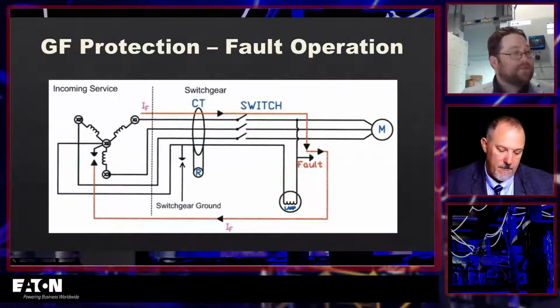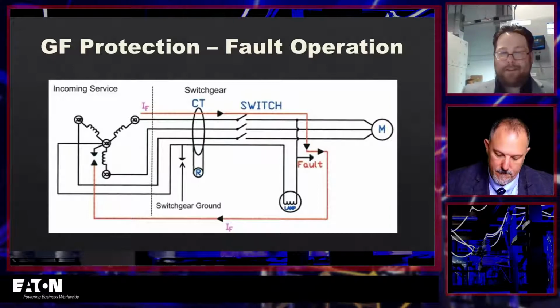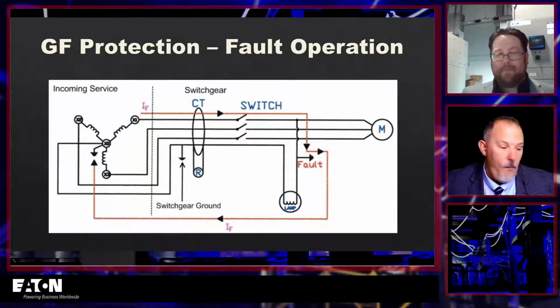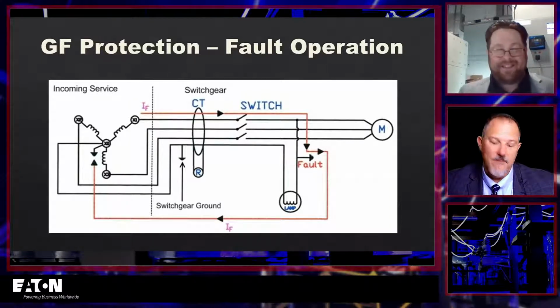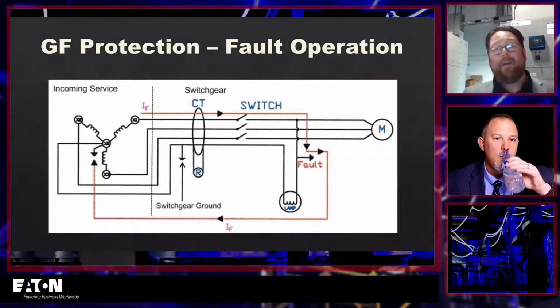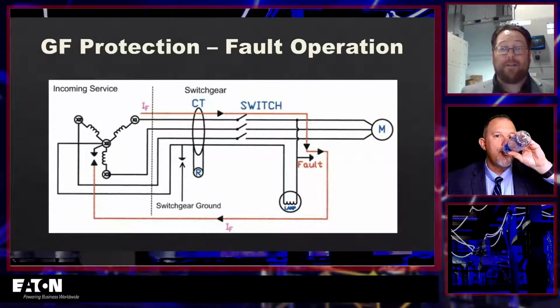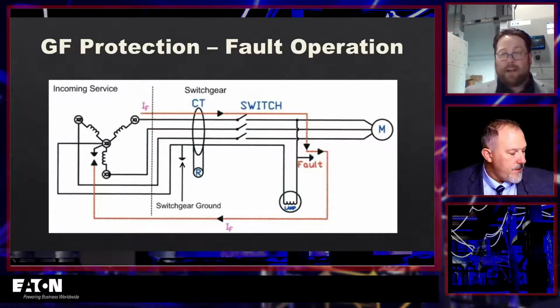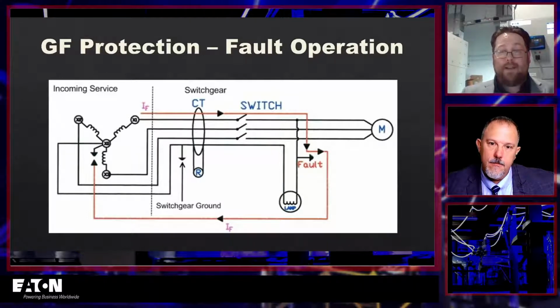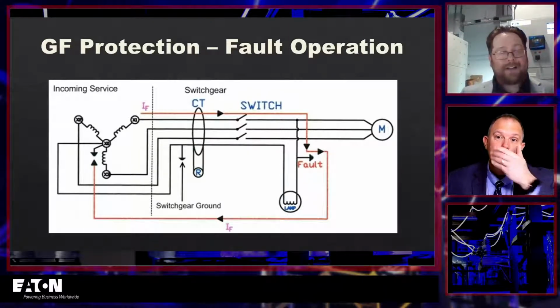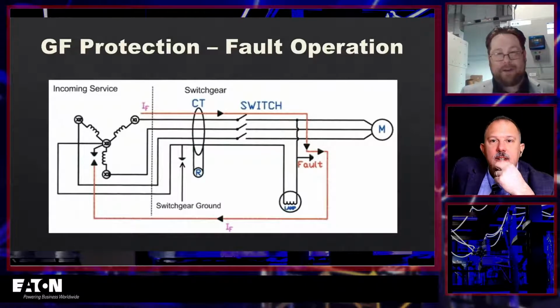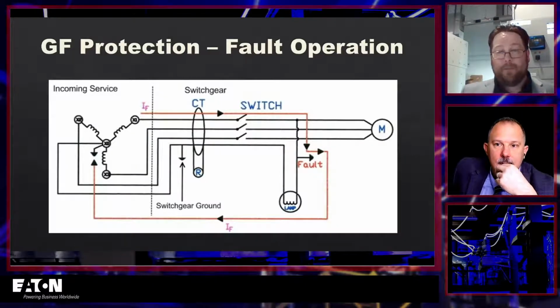Absolutely. Tom, you just made me think of another example in my history. There's a high school right here in Pittsburgh that I won't even name. I got called out there years and years ago to do some power quality measurements because they didn't understand why their ground fault at the main device was tripping. I was able to capture some ground current that would increase, and sure enough, it would trip. They would turn it back on, it would increase, and it would trip.